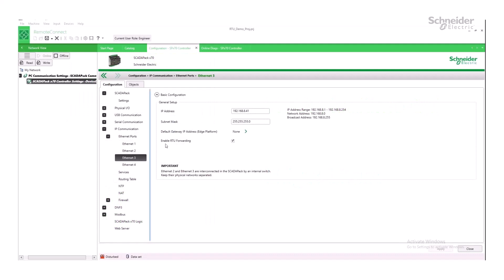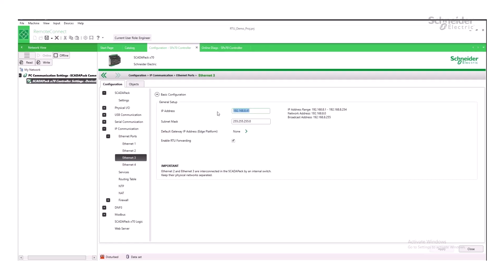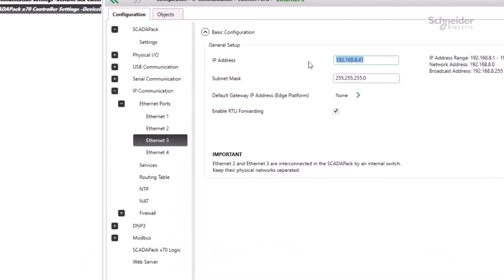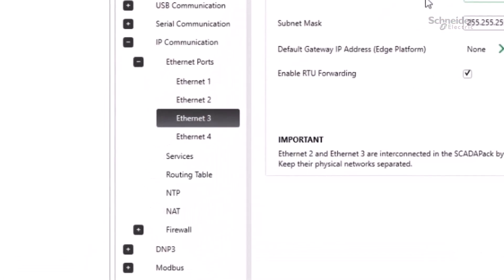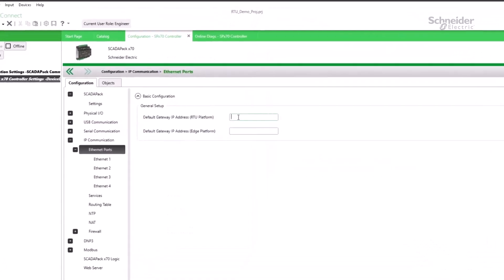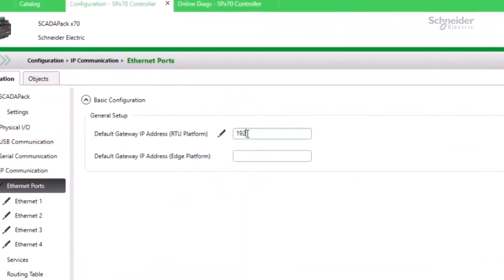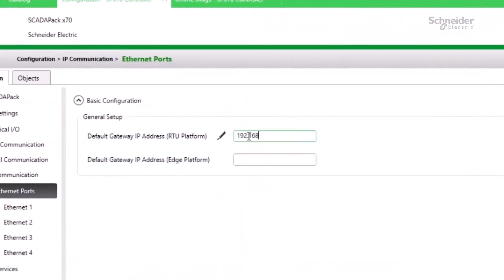In order to use Docker on your SCADAPack, you will have to configure one of the Ethernet ports of your SCADAPack's edgeboard to have an IP address on your router's subnet, but outside your router's DHCP range. In this case, we'll use Ethernet 3.